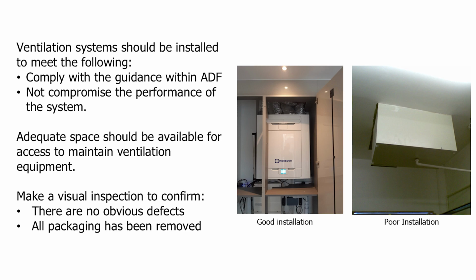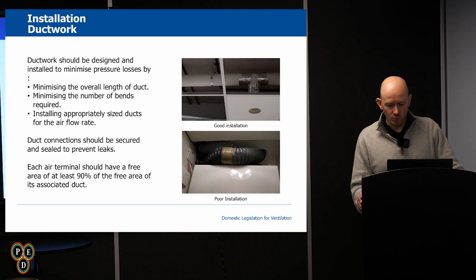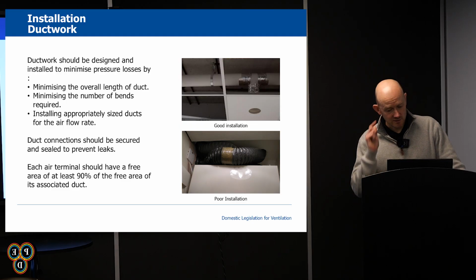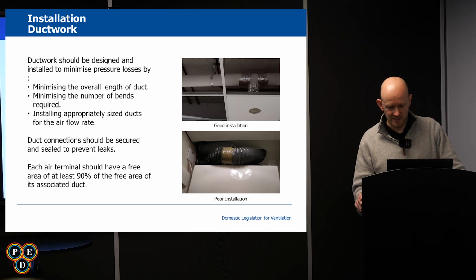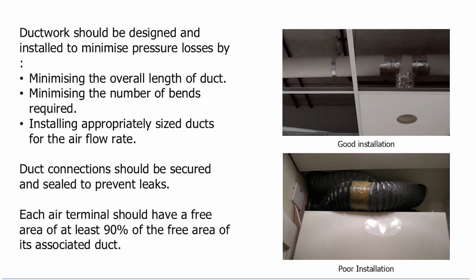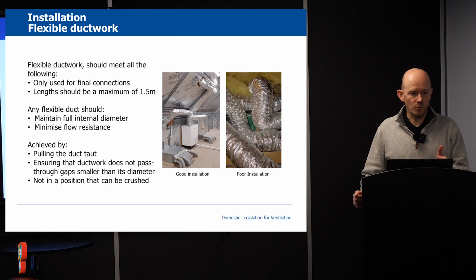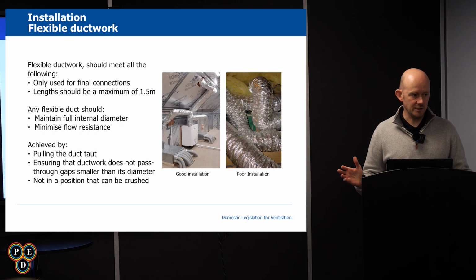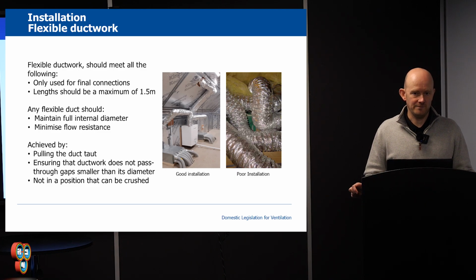It is suggested that rigid ductwork should be used wherever possible, designing to minimise the pressure losses to ensure efficiency and sealed to prevent any leakage. Examples of a good installation with each connection sealed properly compared to a poor installation where flexible duct has been taped together with parcel tape. Regulations up till 2022 said no more than 1.5 metres are flexible on any installation. That was the regs. Then they changed it to minimise where possible, which is very ambiguous.